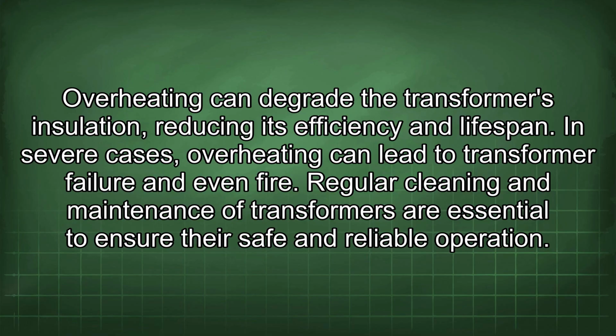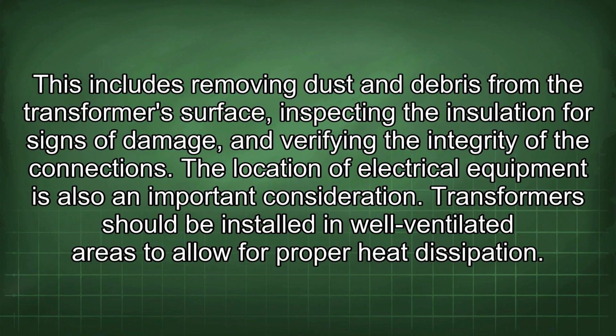In severe cases, overheating can lead to transformer failure and even fire. Regular cleaning and maintenance of transformers are essential to ensure their safe and reliable operation. This includes removing dust and debris from the transformer's surface, inspecting the insulation for signs of damage, and verifying the integrity of the connections. The location of electrical equipment is also an important consideration.